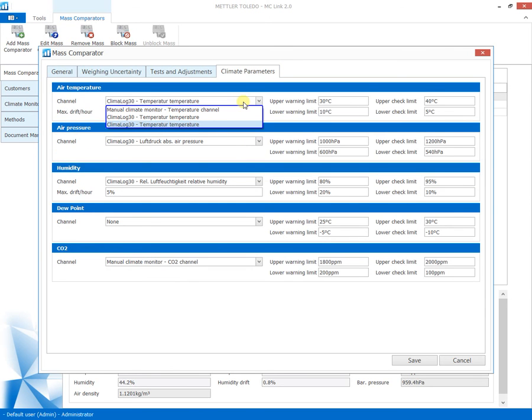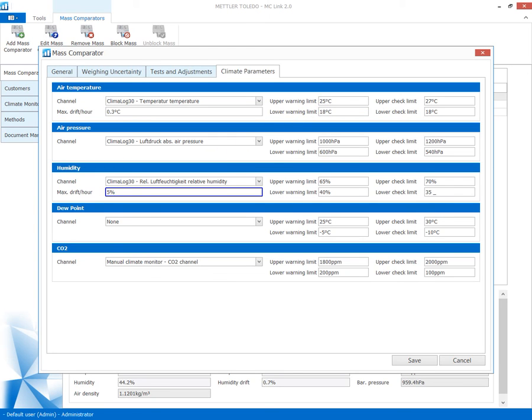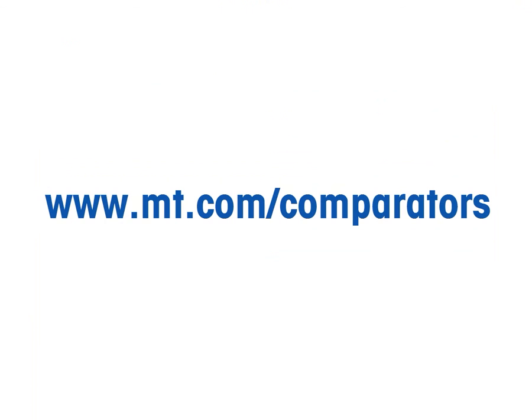Climatic changes influence performance significantly and need to be kept under control. To enable the control and action on climatic fluctuation, for each comparator, limits in fluctuation and range are defined. This assures the required climatic stability during the calibration process. If the limits are exceeded, the comparator is blocked to eliminate the risk of non-reliable data.